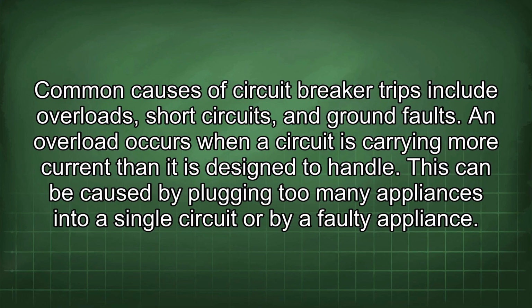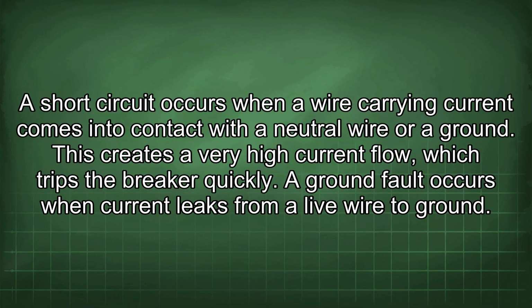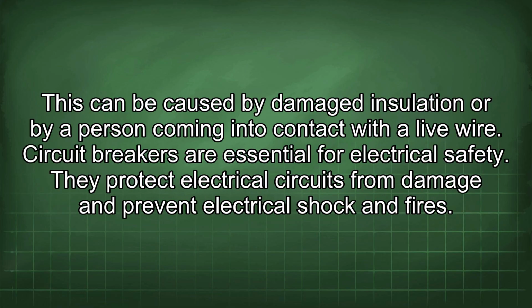An overload occurs when a circuit is carrying more current than it is designed to handle. This can be caused by plugging too many appliances into a single circuit or by a faulty appliance. A short circuit occurs when a wire carrying current comes into contact with a neutral wire or a ground. This creates a very high current flow, which trips the breaker quickly. A ground fault occurs when current leaks from a live wire to ground. This can be caused by damaged insulation or by a person coming into contact with a live wire.